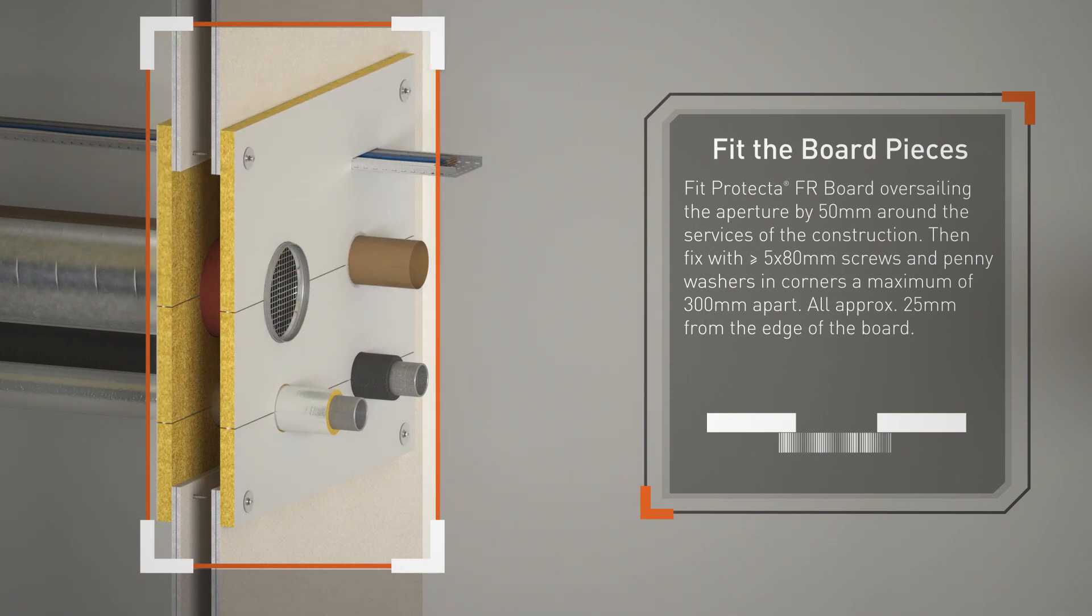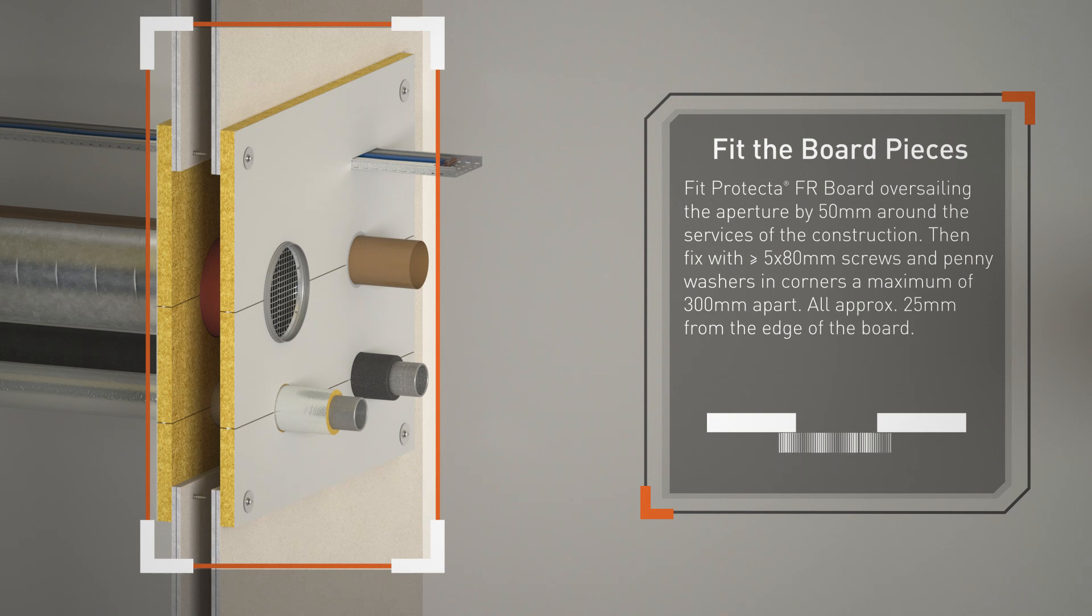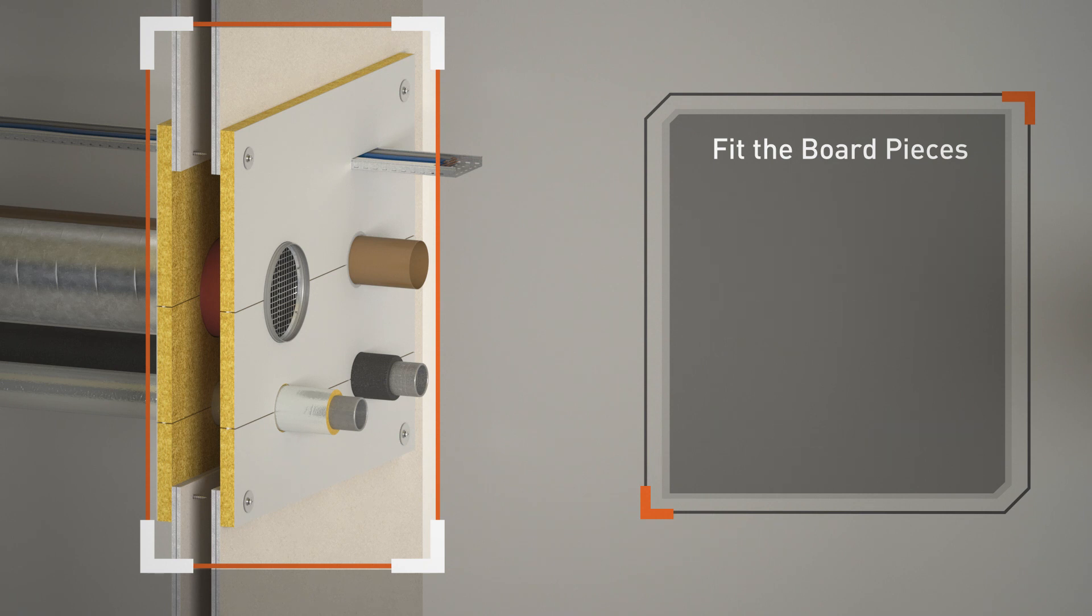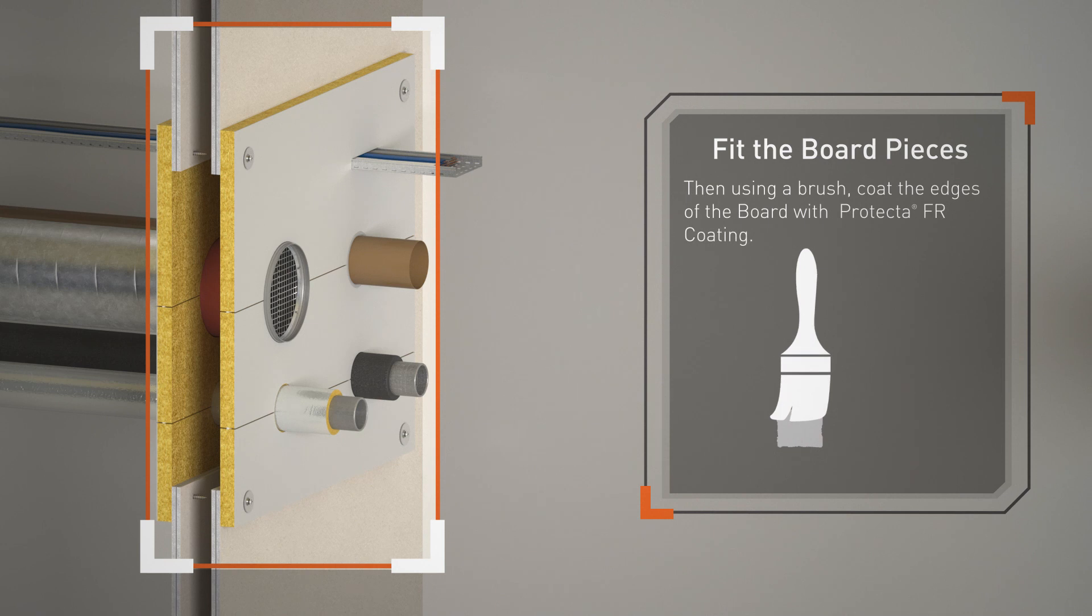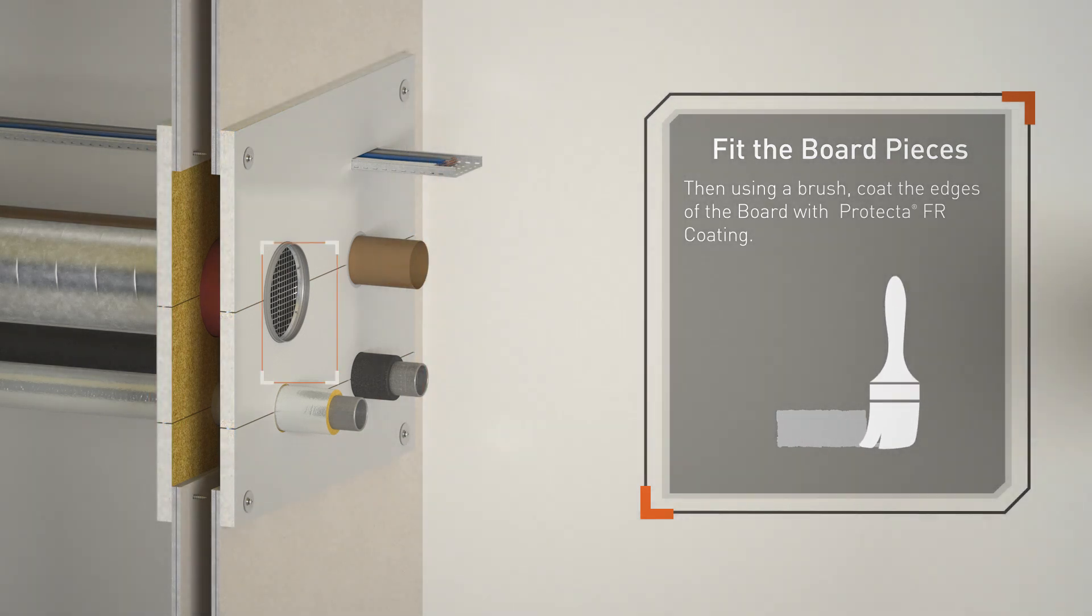Fix with 5 by 80 millimeter screws and penny washers in corners, a maximum of 300 millimeters apart, approximately 25 millimeters from the edge of the board. Then, using a brush, coat the edges of the board with Protecta FR coating.